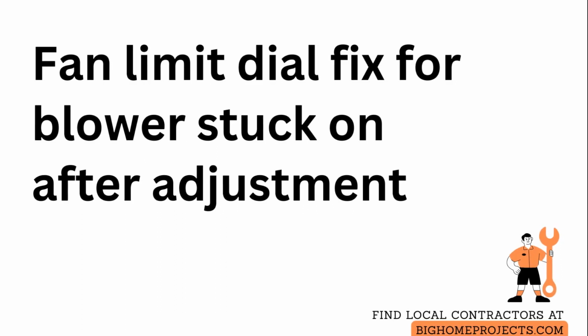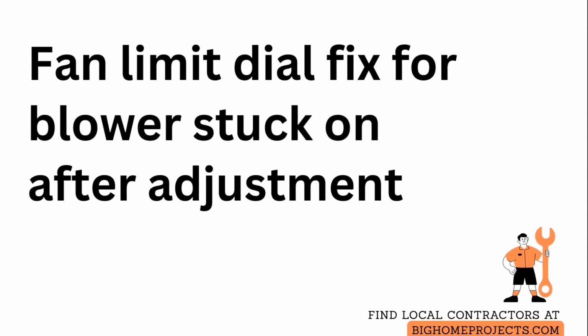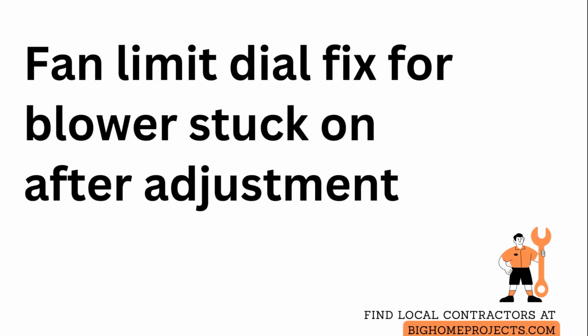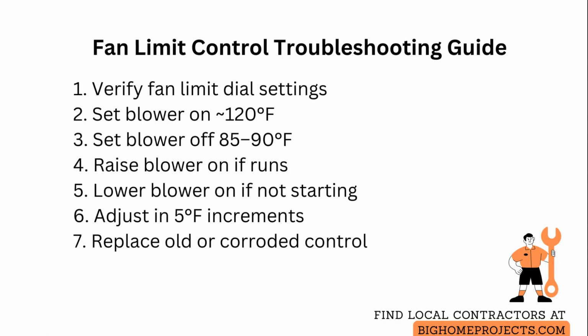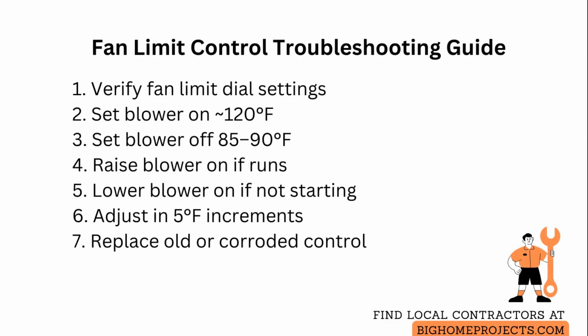If your fan limit control will not turn off the blower, check the dial settings and calibration immediately. The fan limit control is a temperature-sensitive switch mounted on the furnace that tells the blower when to start and stop based on plenum temperature.